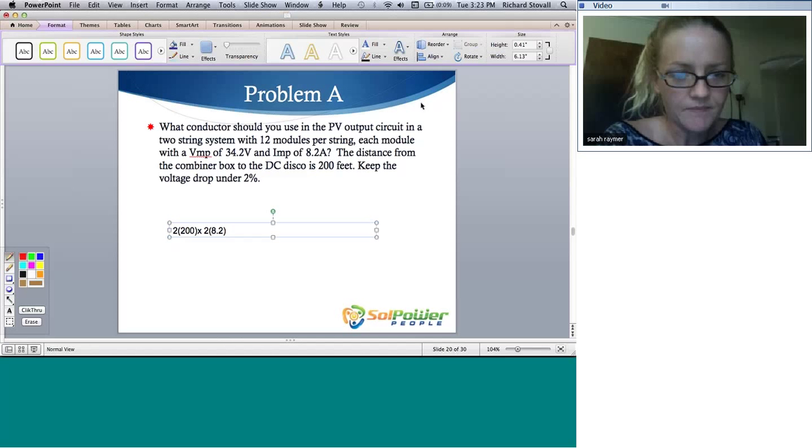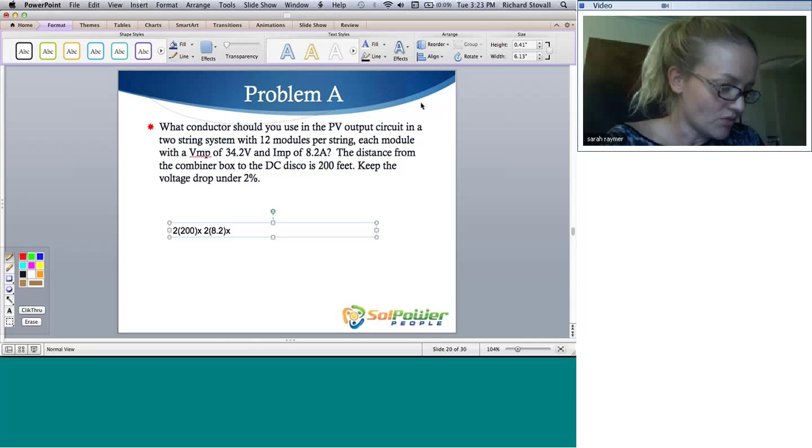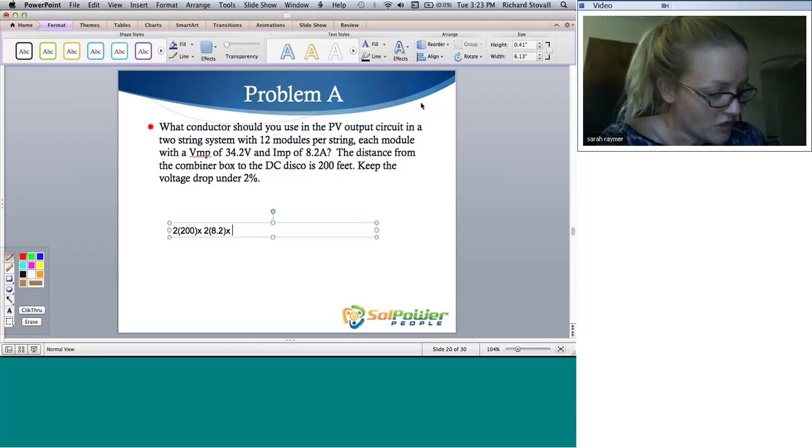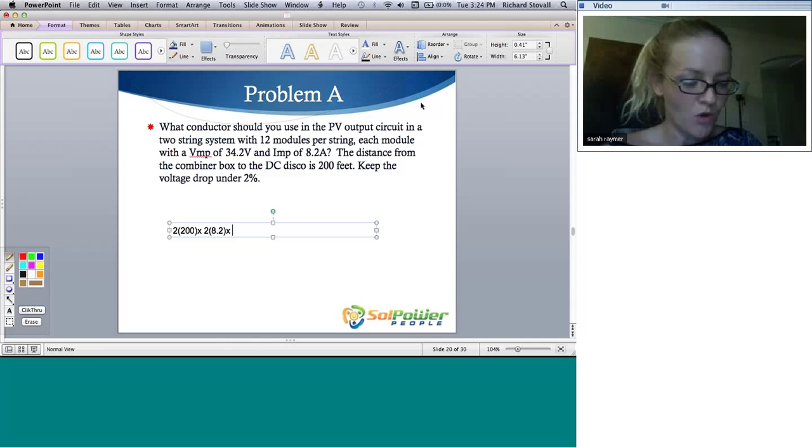And that's going to be multiplied by our ohms per kilofoot. So I like to work through it with a few different ones and figure out which one's right. So I'm going to go ahead and just start with a number 10. What I did was I took a handy little post-it and I wrote down my ohms per kilofoot for every wire size from 14 to 2 so that I didn't have to keep looking at my code book. So I know that number 10 is a 1.24.